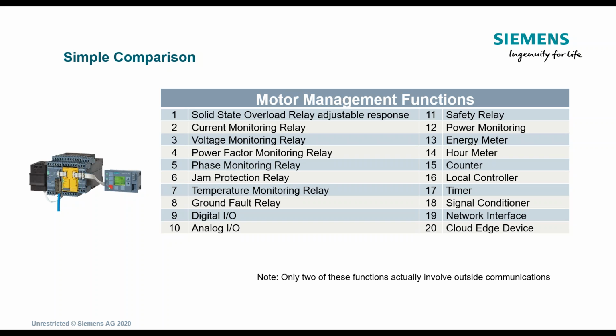So instead of doing that, how about if we have an accumulative hour meter in the SIMOCODE, and once it hits, let's say, 600 hours, it sends a signal to the operator. The operator fills out a work order, sends it to the scheduler to schedule down that motor, hands it to maintenance. Maintenance goes out, does its PMs on it, comes back to the operator, he resets the hour meter, and we're off and running. So let the motor management system dictate when the PMs are taken care of with the hour meter. And then counters.